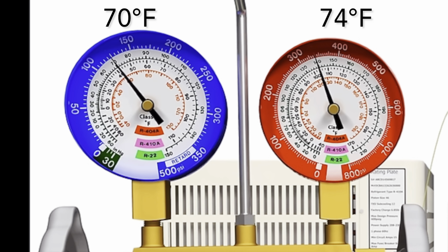So on the low side, you see the saturated temperature of 410A is at 40 degrees, indicating the indoor temperature should be around 70 degrees. The high side, the saturated temperature for 410A is at about 104 degrees, indicating a 74 degree outdoor air temperature. By knowing both the indoor and outdoor air temperature, you have a target or an idea of where your refrigerant pressures and saturated temperatures should be before you even hook up your gauges.